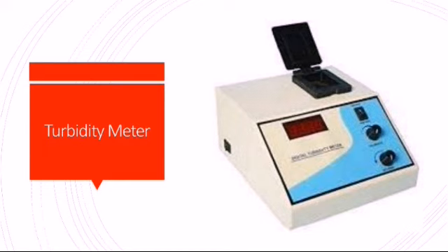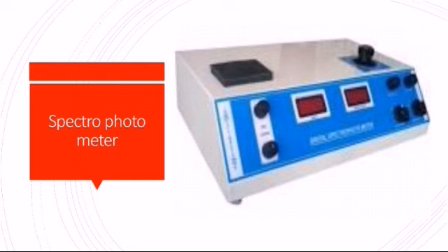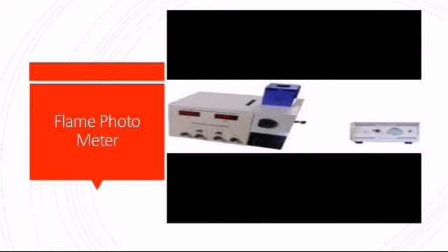Spectrophotometer. Spectrophotometry is the quantitative measurement of the reflection or transmission properties of a material as a function of wavelength. It is more specific than the general term electromagnetic spectroscopy in that spectrophotometry deals with visible light, near ultraviolet, and near infrared, but does not cover time-resolved spectroscopic techniques. Flame photometer. Photoelectric flame photometer is a device used in inorganic chemical analysis to determine the concentration of certain metal ions, among them sodium, potassium, lithium, and calcium. Group 1 and Group 2 metals are quite sensitive to flame photometry due to their low excitation energies. In principle, it is a controlled flame test with the intensity of the flame color quantified by photoelectric circuitry.